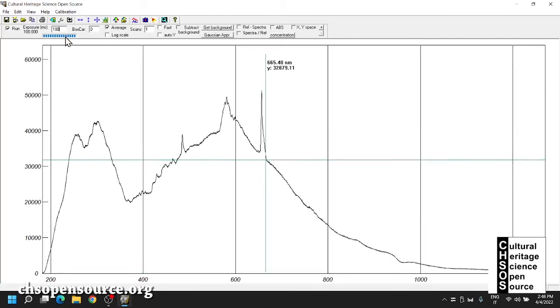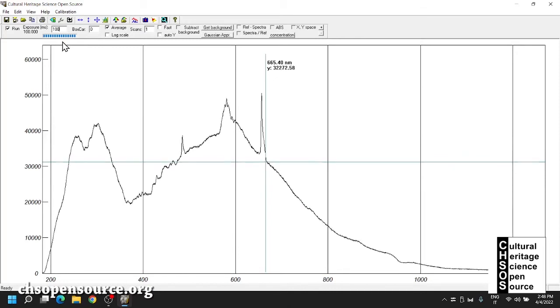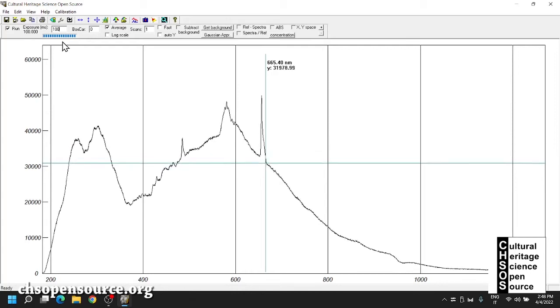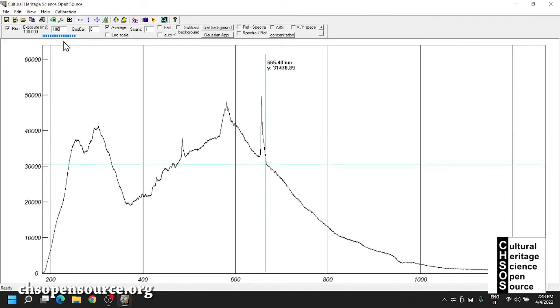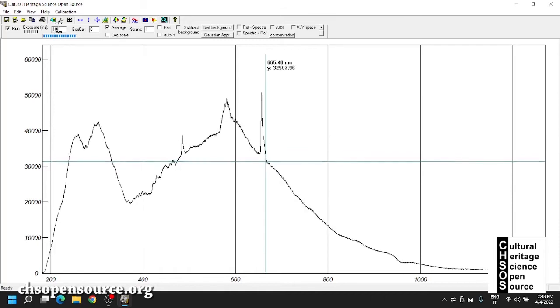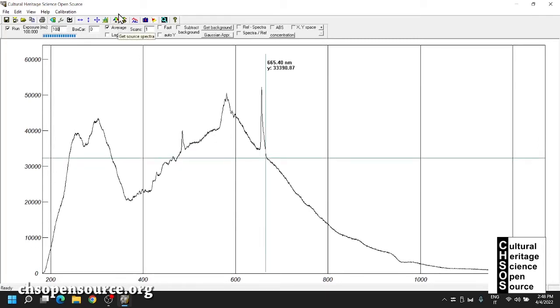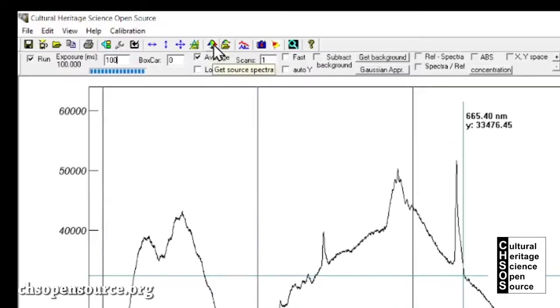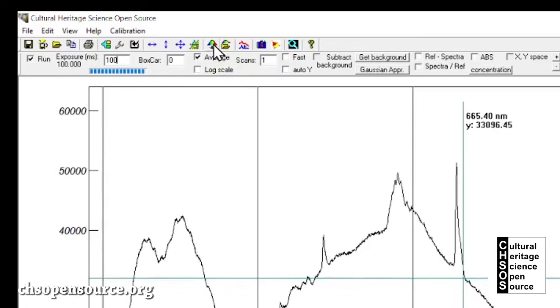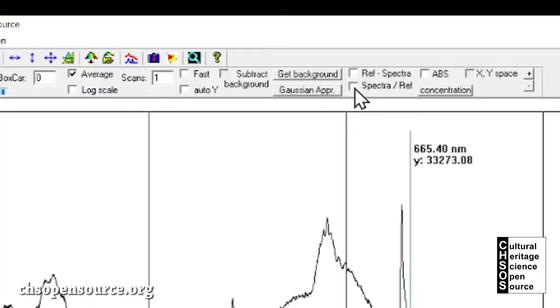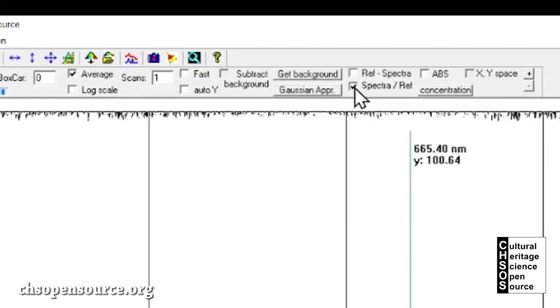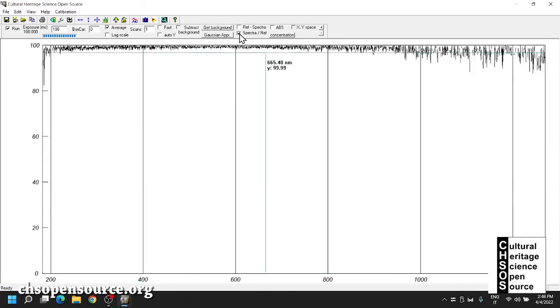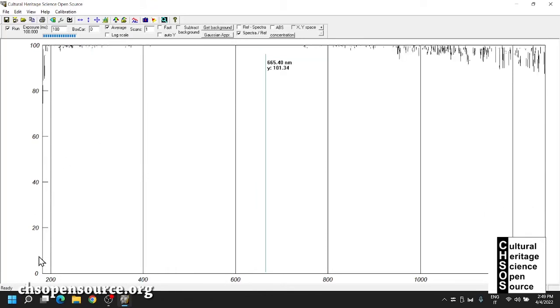So we can keep 100 milliseconds as the exposure time. Again, I put the probe at about 45 degrees, and well, it's a good idea to wait about 5 minutes once the lamps are on. So we wait for them to warm up enough, so they are more stable. Okay, in this case, anyway, we had some minutes, we've been talking. So to do the calibration, remember, we click this button over here, File, Get Source Spectrum. So we click it, and then, as usual, we go into Spectra/Reference.